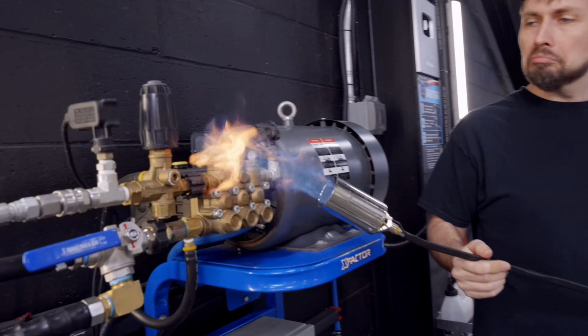So these switches are both at rest right now, so we can test them to see which is normally open and which is normally closed. The blue is the common. This one is normally closed, and that's what we want on the outlet. Normally open with blue and brown goes on the one on the pump head here.